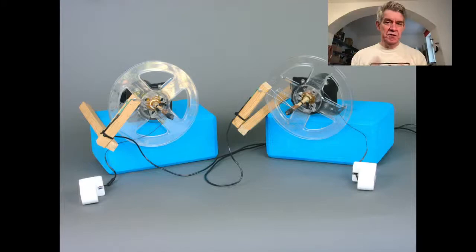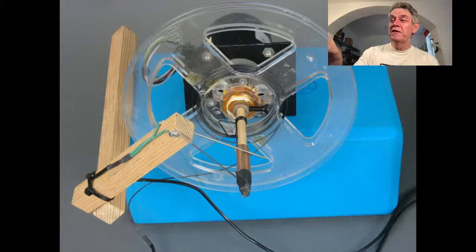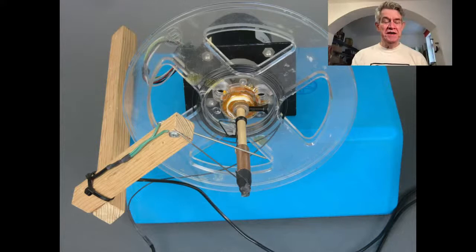The really absolutely frightening part of this thing, so if you look carefully, you see on the wood there are two wires, and they are touching a piece of copper pipe, which is on a piece of wood. Notice that that's wood going to the motor there. So that copper pipe is attached to the wire that is wrapped around the reel going down to the fluorescent light. In other words, this is what was up in the grid. That was absolutely bare. The electricity coming from the ballast that ran the fluorescent lights was just sitting there with those wires touching it. And I don't know, nobody ever asked us any questions, but probably that isn't exactly safe.